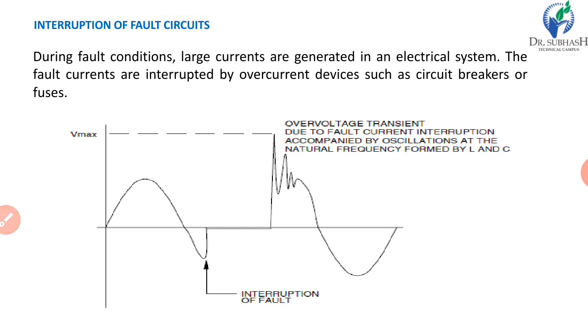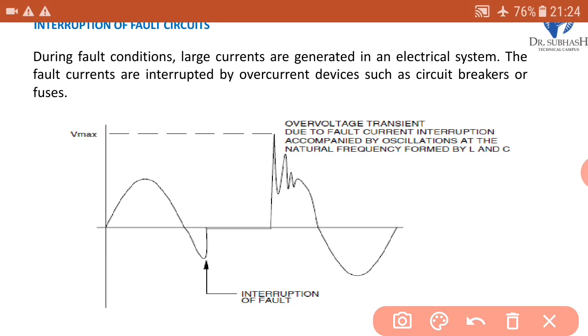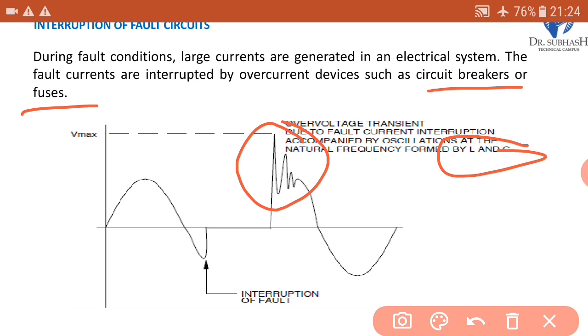Another one is interruption of fault currents. During fault conditions, large currents are generated in the electrical system. The fault currents are interrupted by overcurrent devices such as circuit breakers or fuses. In this figure, we can see a transient is generated, and it is oscillatory in nature. So the overvoltage transient due to fault current interruption is accompanied by oscillations at the natural frequency formed by L and C. Okay, so whenever an interruption of a fault occurs, a transient may be generated.